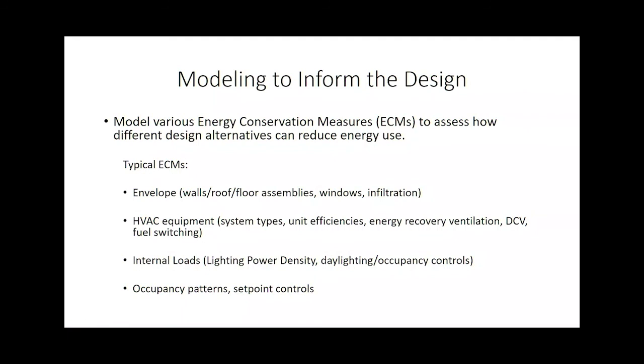Then we also look a lot at internal loads, so lighting power density, and things like daylighting controls or occupancy controls that control either the lighting or plug loads, to get rid of things like phantom loads during unoccupied periods. We also look a lot at occupancy patterns and set point controls.